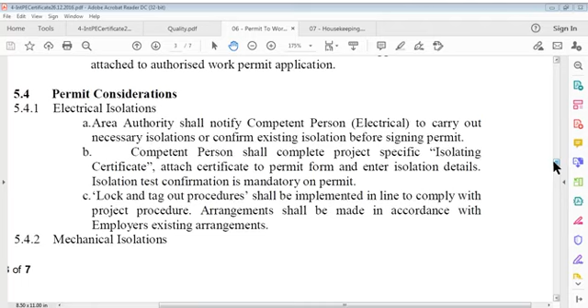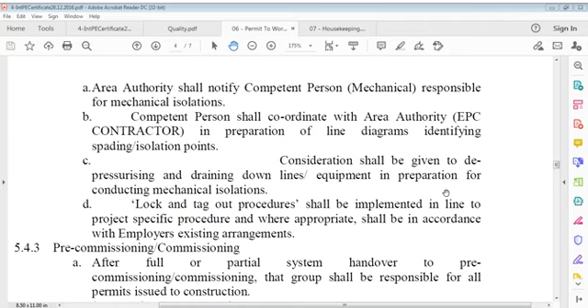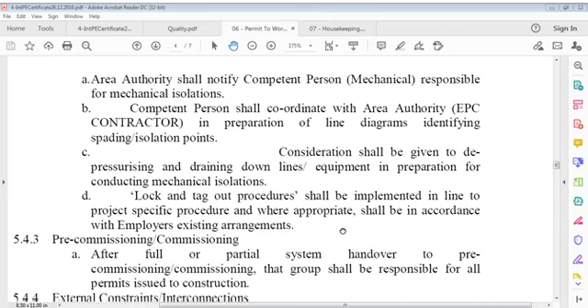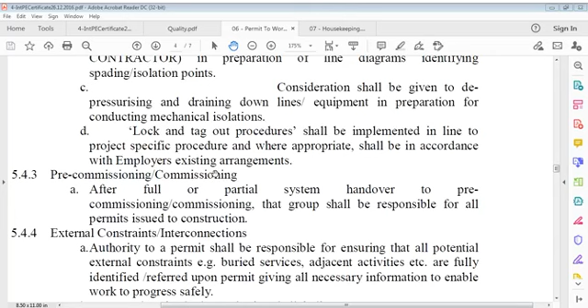Mechanical isolation: the area authority shall notify the competent person, that is mechanical, responsible for mechanical isolation. The competent person shall coordinate with the area authority and EPC contractor in preparing line diagrams identifying isolation points. Consideration shall be given to depressurizing and draining down lines and equipment in preparation for conducting mechanical isolation. Lock and tag out procedures shall be implemented in line with the project specific procedure, and where appropriate shall be in accordance with the employer's existing arrangements.